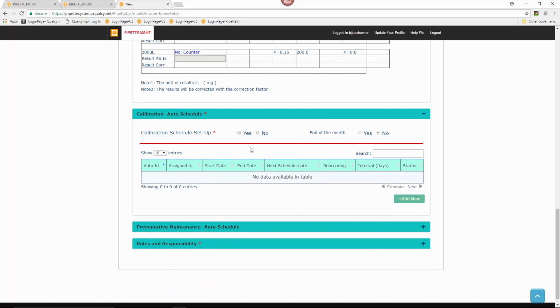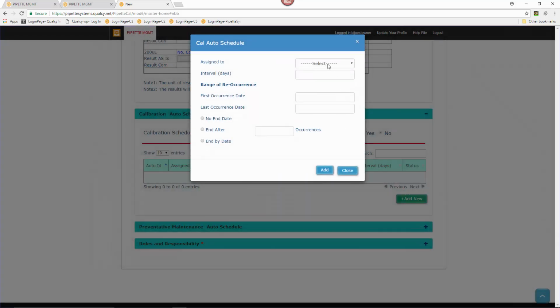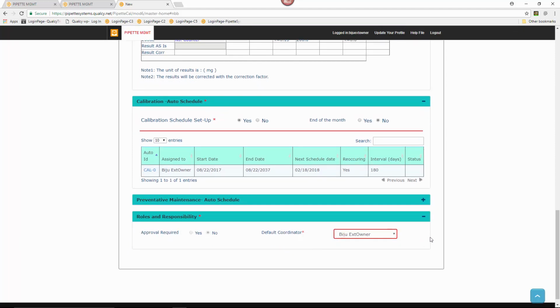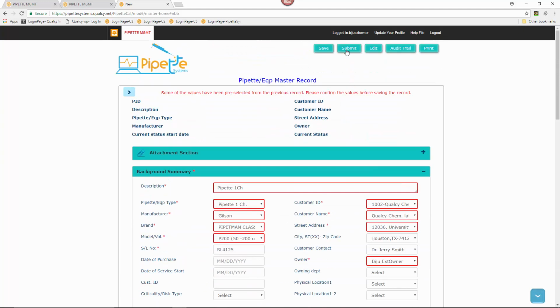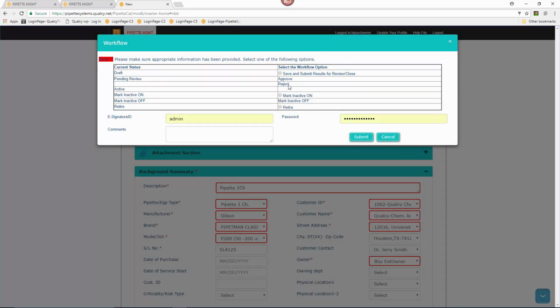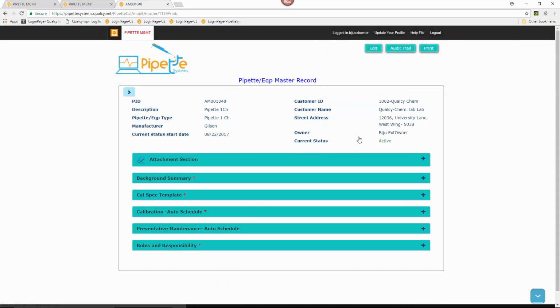So I'm going to select a schedule here also. So add new, assign it to myself, and usually I'm going to put it as 180 days as the interval, so we can select a no end date, and this field is already filled in. So all that I would do is make it active again. I will confirm the data entry. As you saw, it took me less than 1 minute to register the pipette, and now I'm ready to do the calibration of these pipettes.